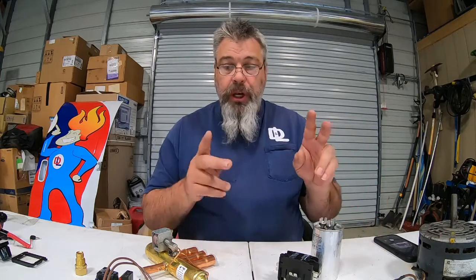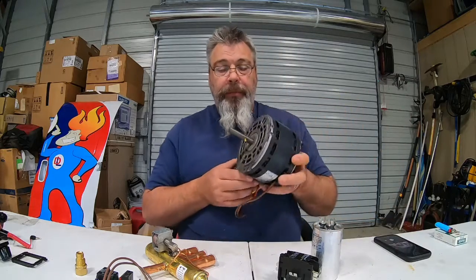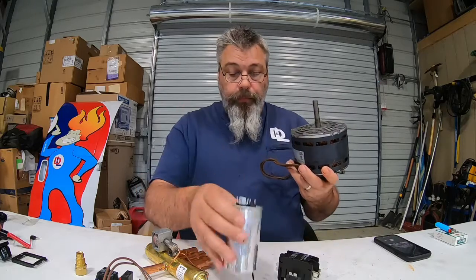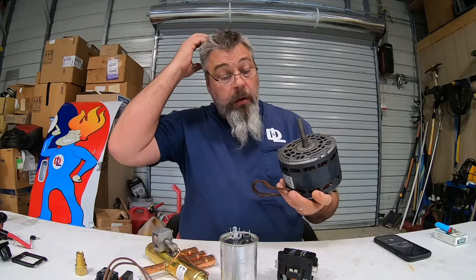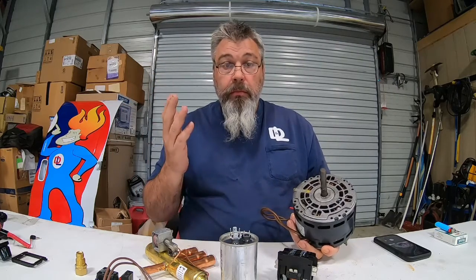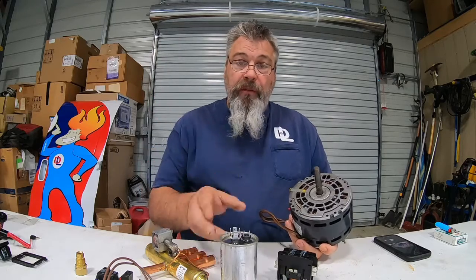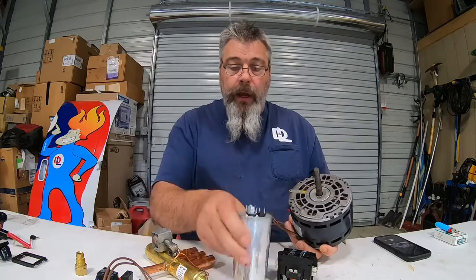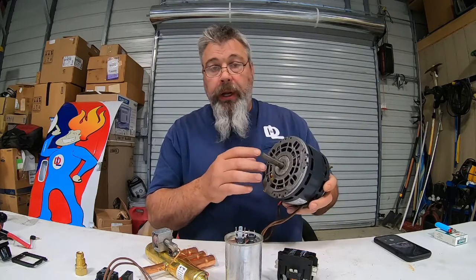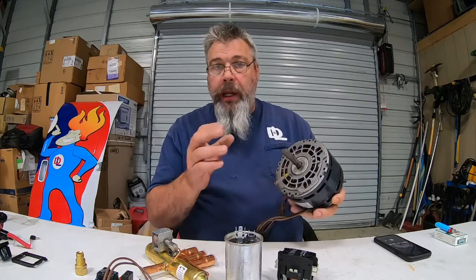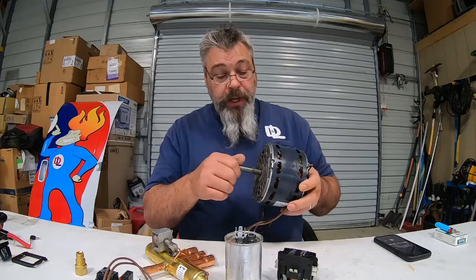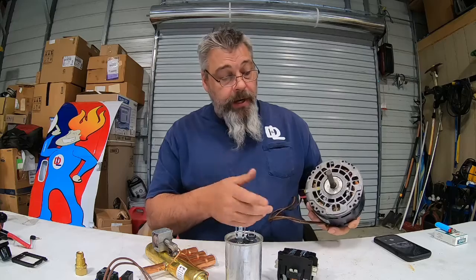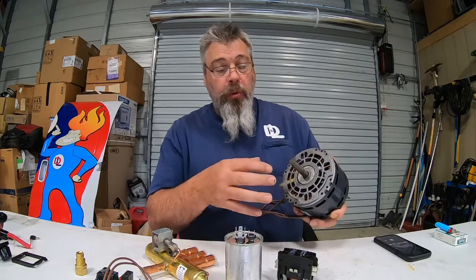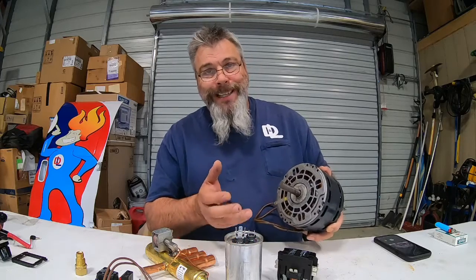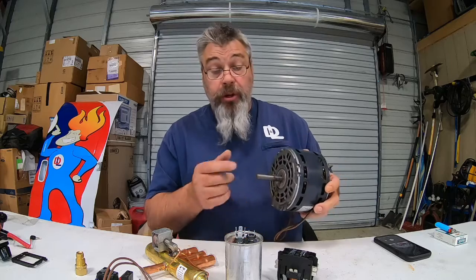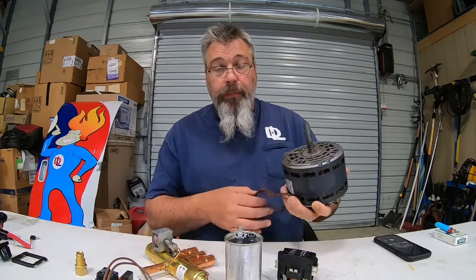The last thing I want to talk about, well, two things. One of the things is a condensing fan motor, okay? Along with that capacitor and the contactor and all these components I talked about, they all operate off the same power. So if one fails, like this, there could be a reason behind that. That reason could be a weak stator inside your motor, weak windings. We always want to check these out. This, however, is an indoor fan motor, and the reason I can tell is that this is all open. On an indoor fan motor, we'll have open vanes to keep it cool. On an outdoor condensing fan motor, this will all be enclosed, because if it rains, you don't want water getting in there. So these will all be enclosed together, okay?